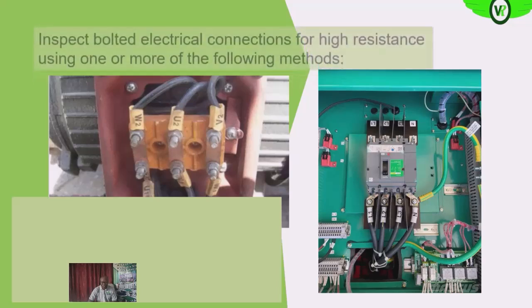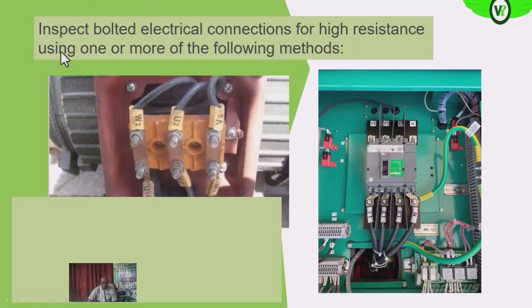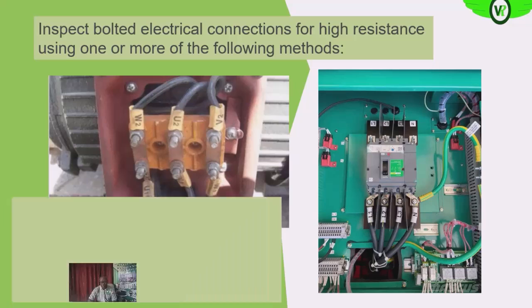So you also need to make visual inspection of those electrical connections to see that there are no signs of high resistance. Okay, all of these connections. Like we discussed in our earlier series, the signs of high resistance are usually those metal oxide deposits, those whitish and greenish substances. So if you see them on these terminals, that goes to show that we have a kind of hot spot around that terminal, which may be as a result of loose contact. Those are signs of high resistance.